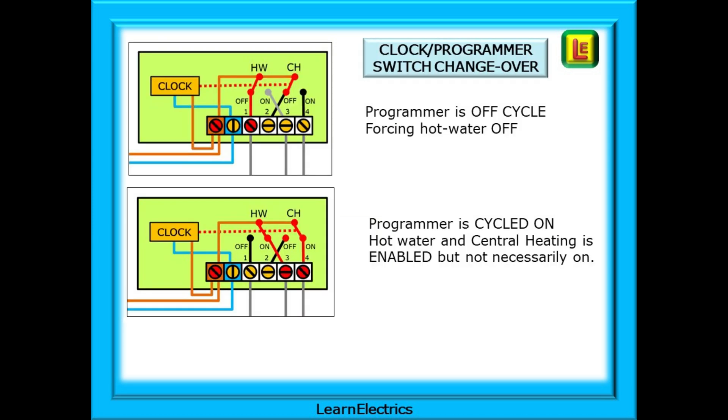The programmer timer and clock have changeover switches that allow us to set the on and off times for the hot water and central heating. In the off cycle periods, 240 volts is on programmer terminal number 1, forcing the hot water off. More on this soon. When the programmer is cycled on, the hot water and/or the central heating switches change over depending on how the programmer is set. This will enable the hot water and/or the central heating, but the boiler will not turn on until one or other of the thermostats calls for the boiler to be on.